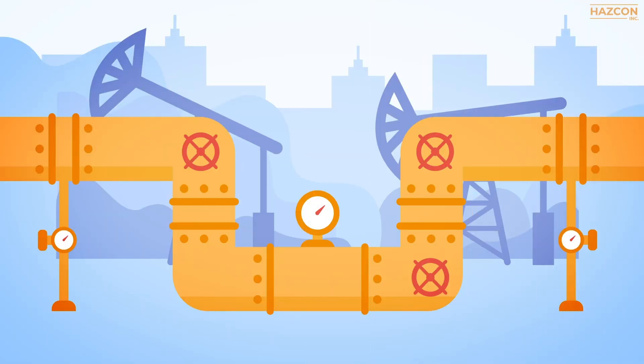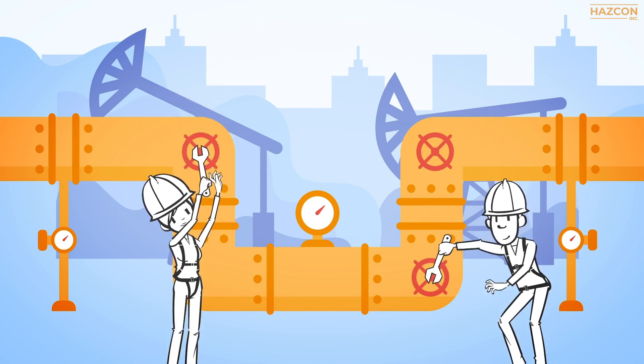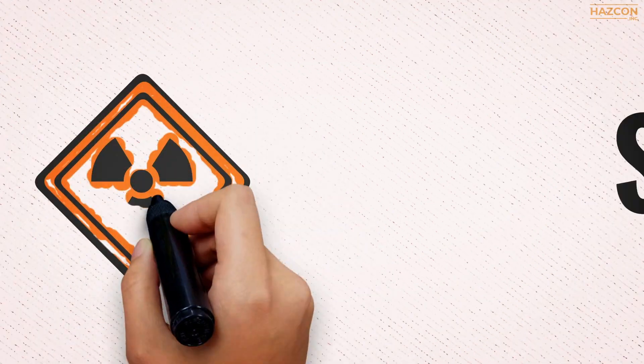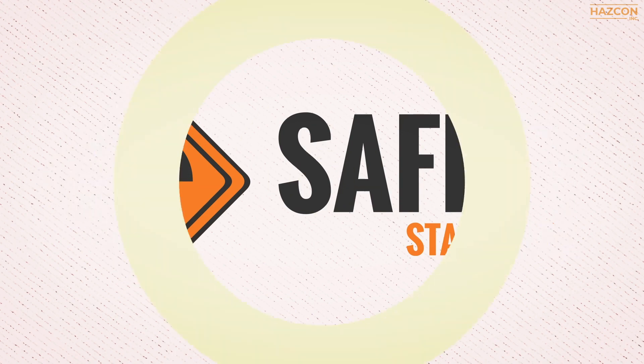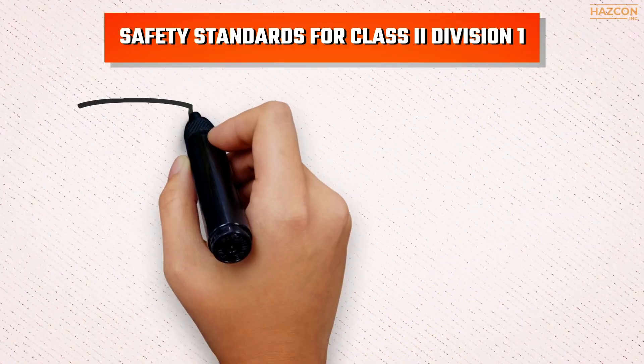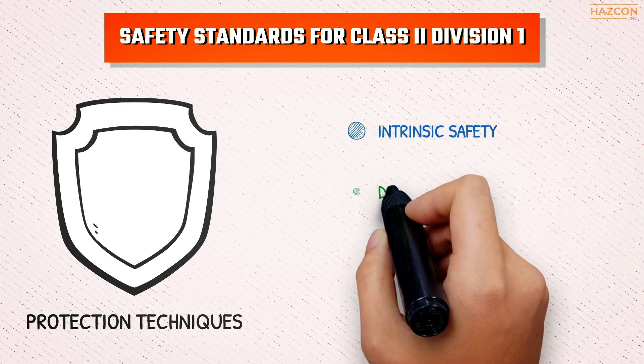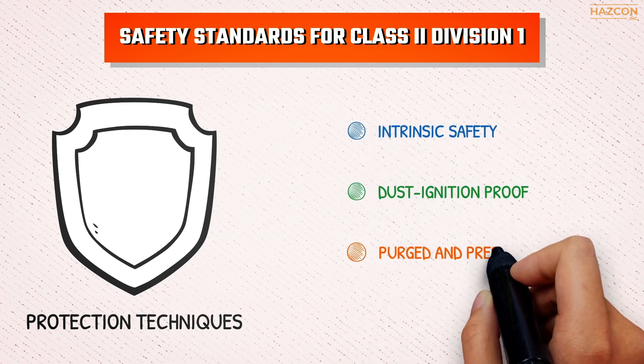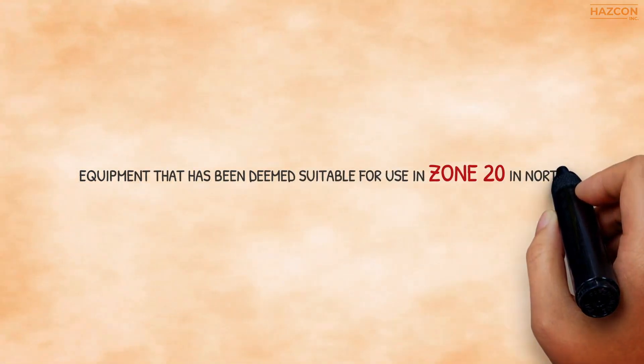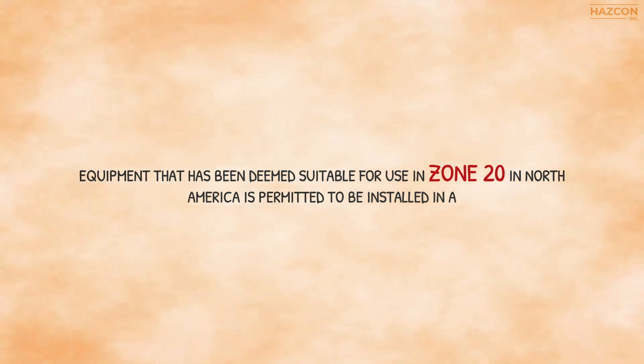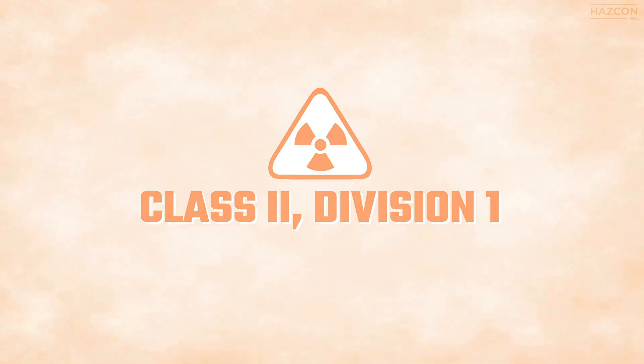Electrical equipment still needs to be installed in hazardous locations where explosive dusts are present. This equipment must therefore be designed, constructed, and certified in compliance with the relevant safety standards. As noted in the standards, Class 2 Division 1 products must be protected by one or more of the following three protection techniques: intrinsic safety, dust ignition proof, and purged and pressurized Type X or Y. Equipment deemed suitable for use in Zone 20 in North America is also permitted to be installed in a Class 2 Division 1 hazardous location.